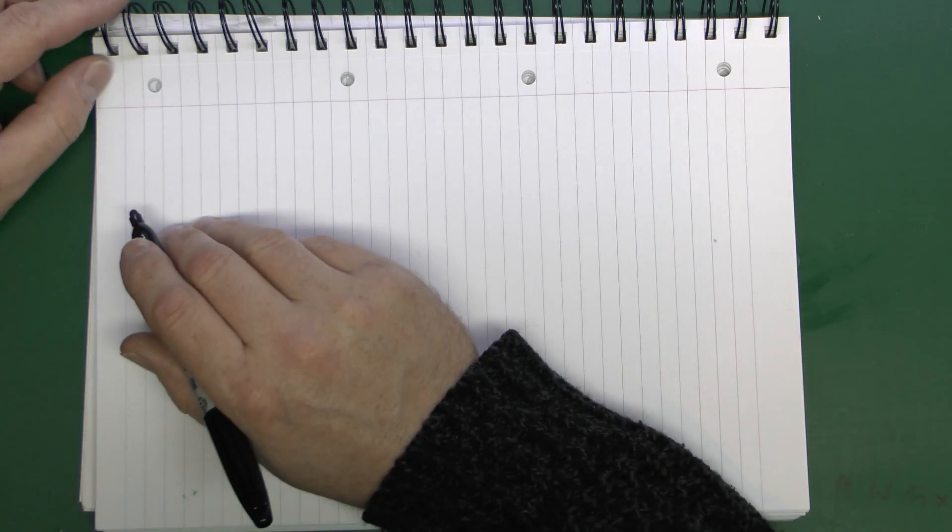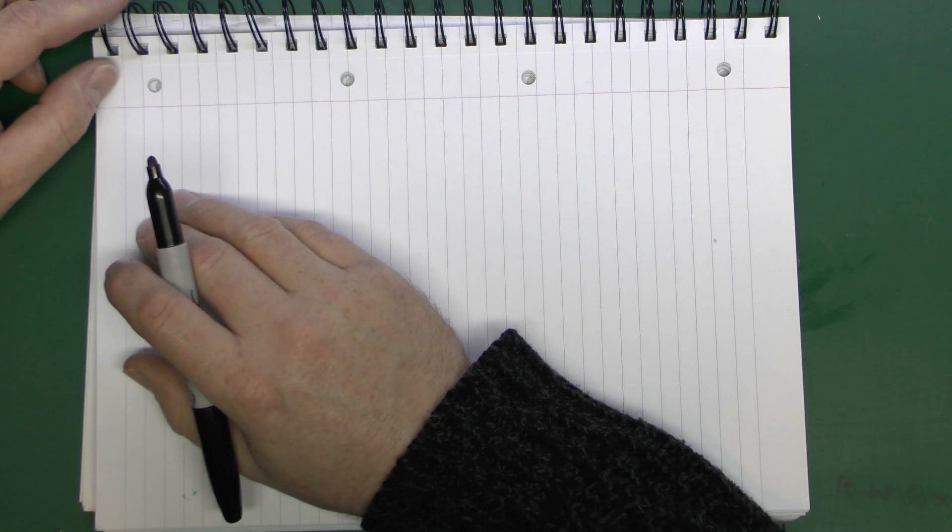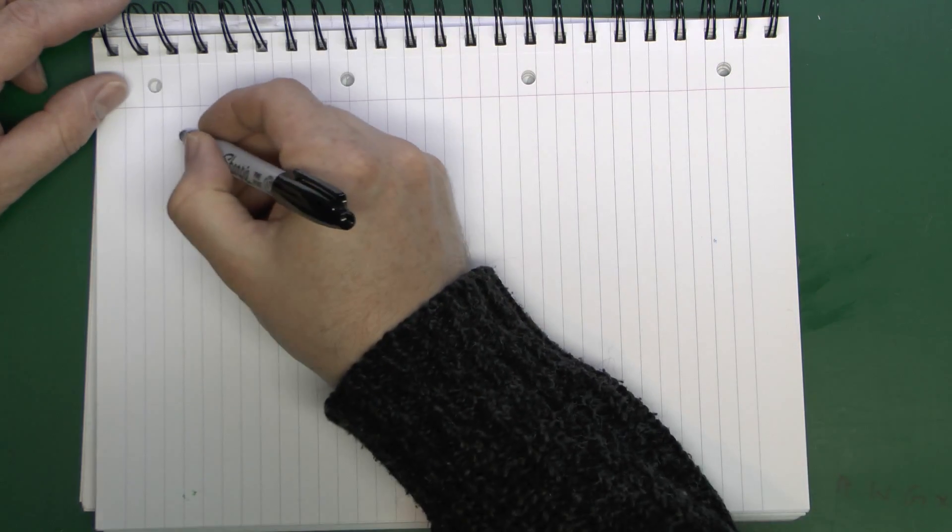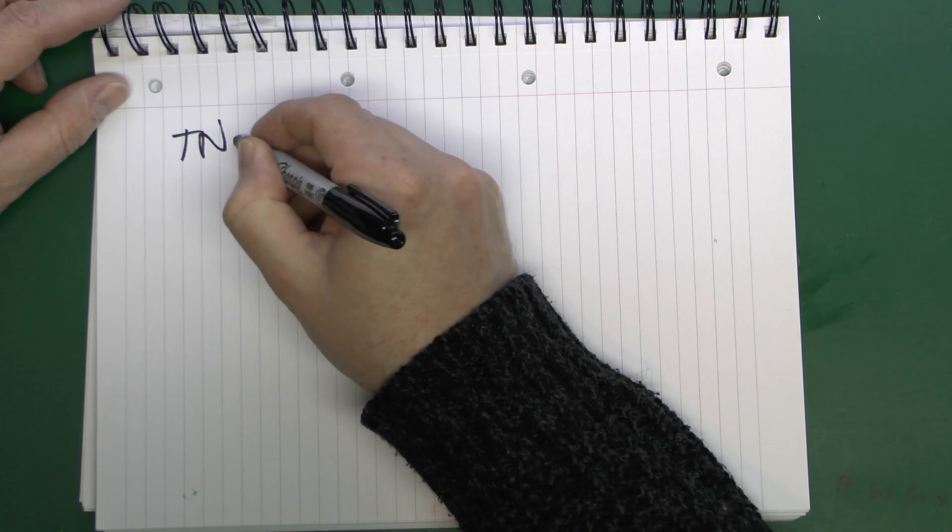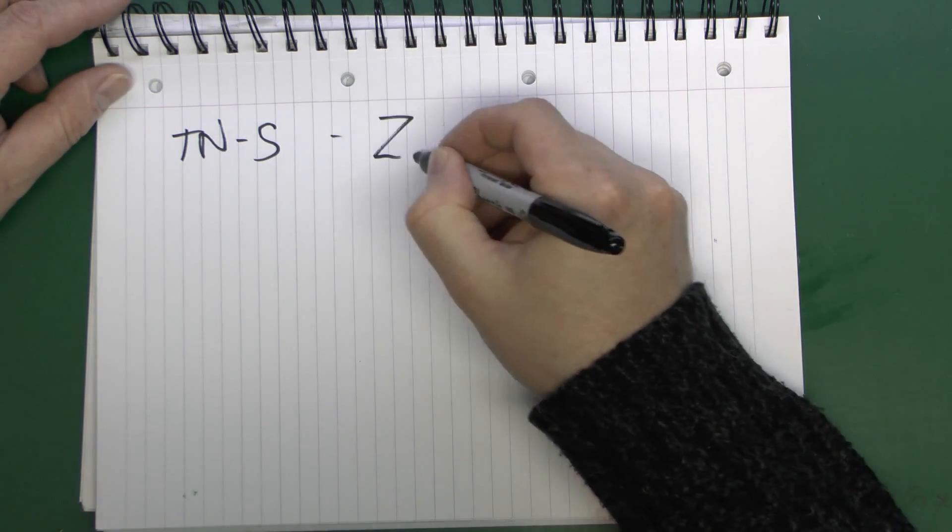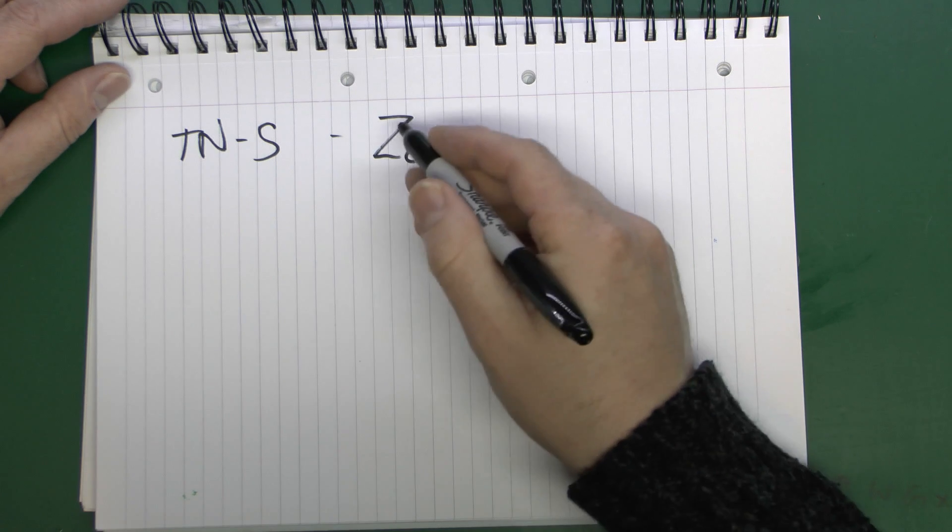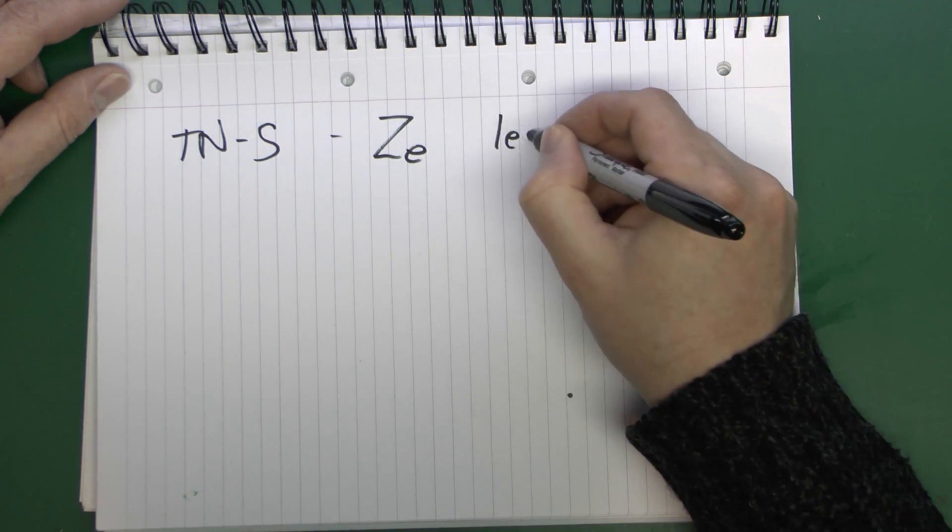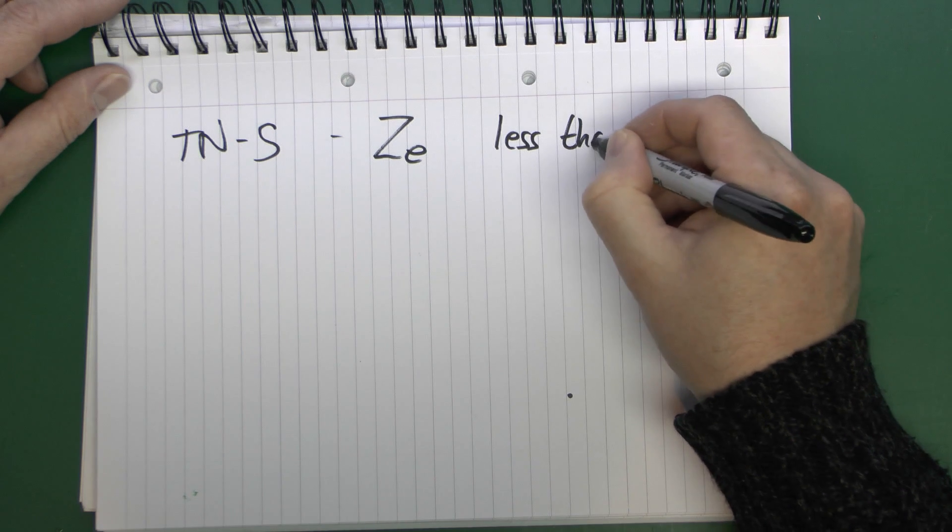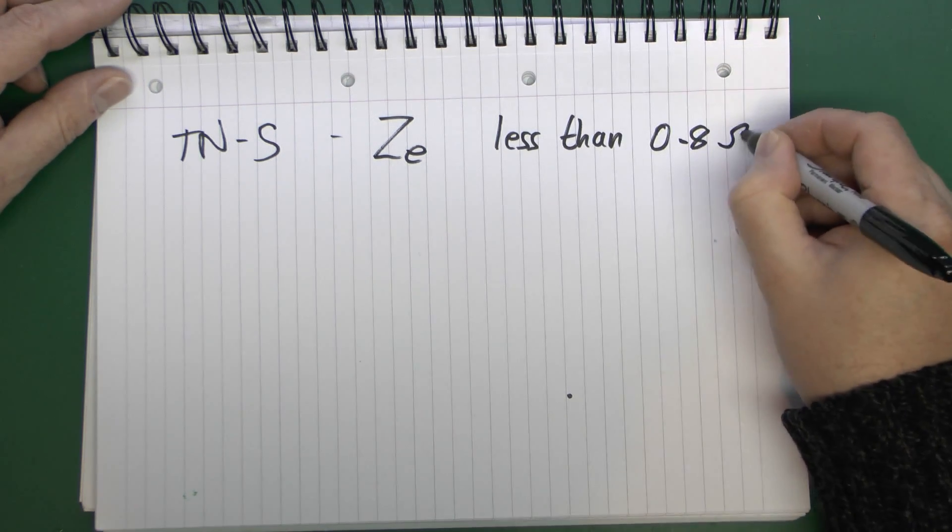Now in terms of what sort of values you should be getting, impedance is measured in ohms as it's a kind of resistance. Depending on the type of earth you have, the values you want to see are within the sort of ranges. So if you have a TNS supply, and that's what we had previously with the separate conductor basically being the outer covering of the cable, then the external impedance or ZE should be less than 0.8 ohms.